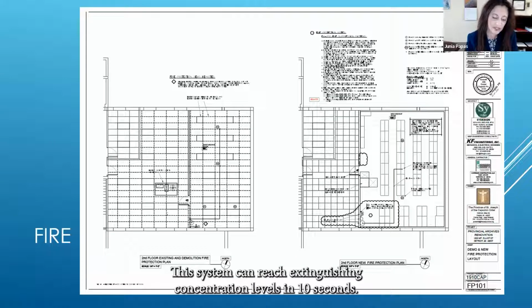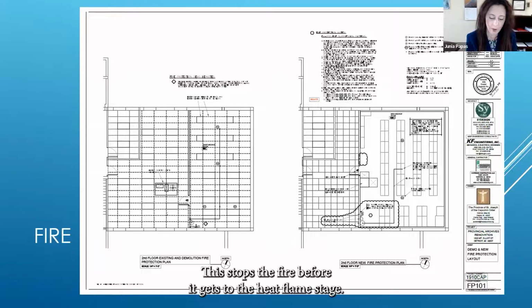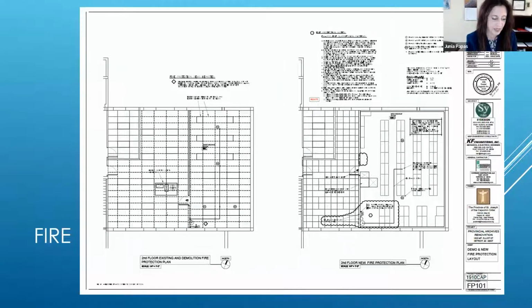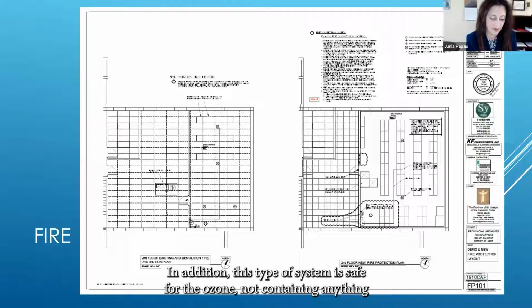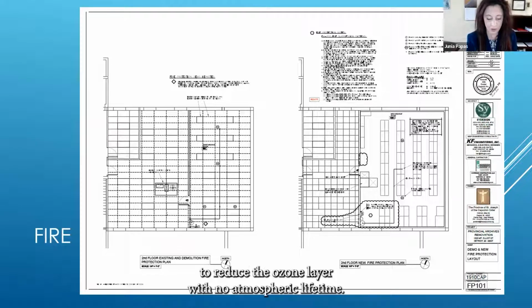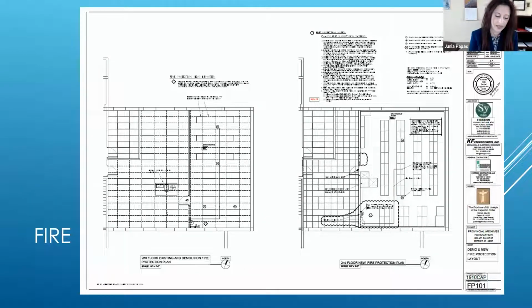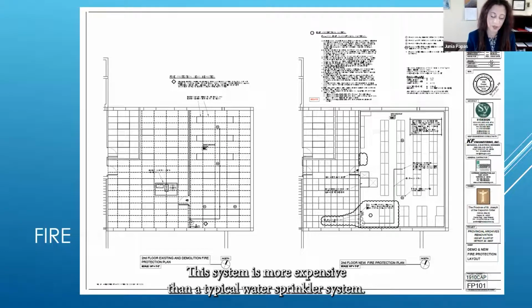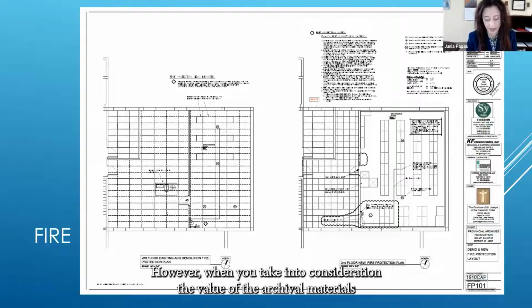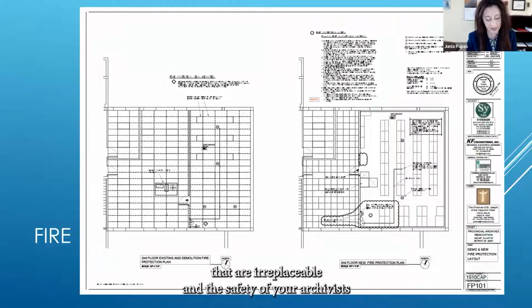This system can reach extinguishing concentration levels in 10 seconds. This stops a fire before it gets to the heat flame stage. In addition, this type of system is safe for the ozone, not containing anything to reduce the ozone layer, with no atmospheric lifetime. This system is more expensive than a typical water sprinkler system. However, when you take into consideration the value of the archival materials that are irreplaceable and the safety of your archivists from potential suffocation from other gaseous fire suppression agents, the decision to go with the fluorinated ketone is worth the money.